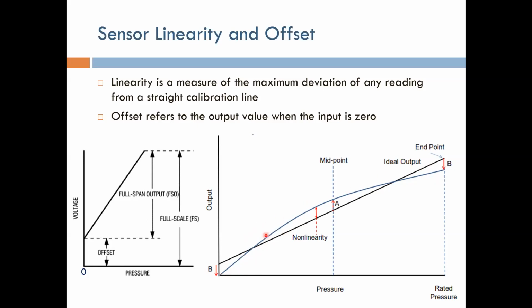The linearity can be measured by the deviation of the curve, in the range that you want to measure, from the ideal linear curve. We have to understand that it's never going to be exactly linear. So it's going to look something like this. The maximum deviation here, around the point that you're trying to measure around, is a measure of the linearity, okay? So how you measure linearity is the maximum deviation. This means that if you're trying to measure over this range, the maximum deviation from linearity that you're going to get is this much value, okay? So the closer this curve gets to this curve, the higher the linearity will be, okay? If you just assume that we have the linear curve, it would look like this.